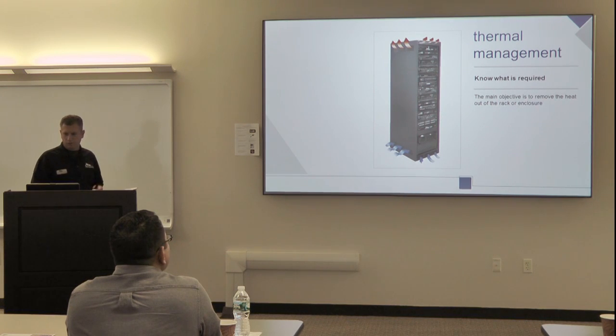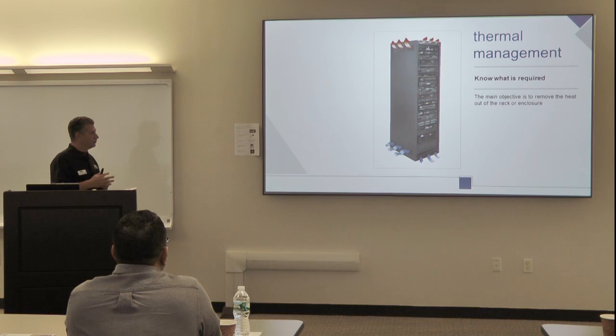So knowing what's required, one of the main objectives of thermal management is to get the heat out of the rack. It's much easier to let a rack do what it naturally does, let the heat rise and come out. You can help that with maybe some fans, but the key is to get the heat out. A lot of guys will say, let me just pump air conditioning into the rack, but you still have to get that heat out of it. So the best thing to remember is just to get the heat out. That's the first thing you want to do.